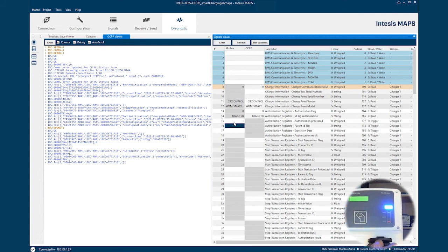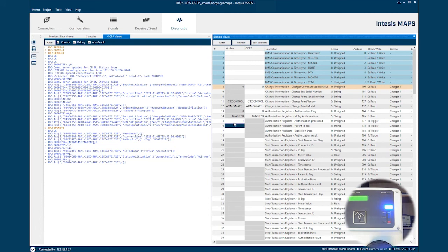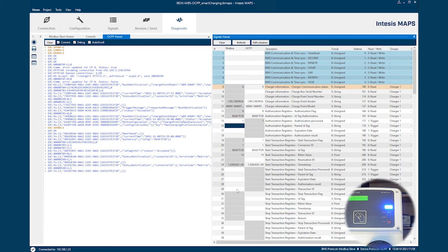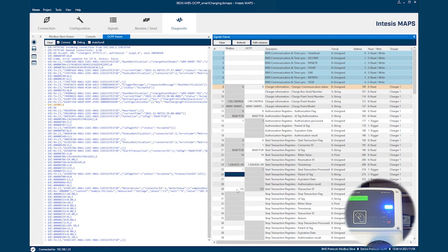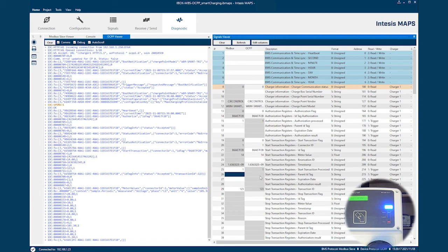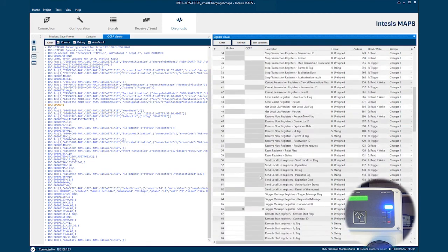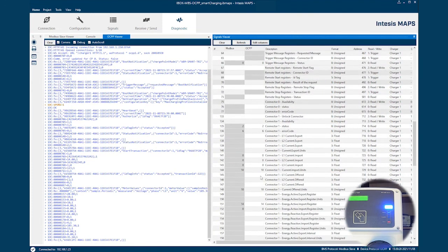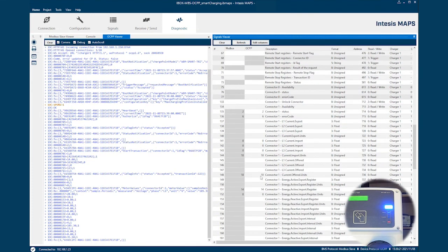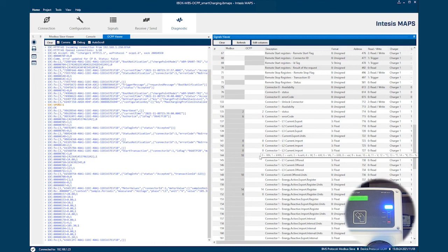We will then connect the plug and the charger will set the start transaction flag and all the registers associated with this transaction as the ID tag, connector ID, meter value, and timestamp. From the BMS, we will then set a transaction ID and set the start transaction process to one. This will automatically clear the start transaction flag. Again, remember to be quick. If doing it manually, if it's done by the BMS, then all that will be automatic. Now we could see here that the status current and other energy values can confirm the charging of my electric vehicle had started and all energy parameters that are currently in use.